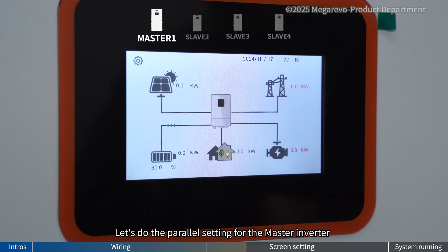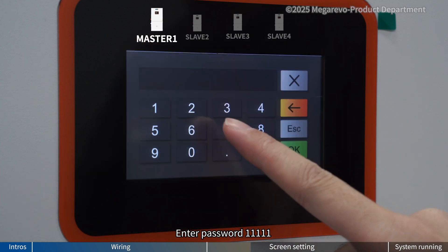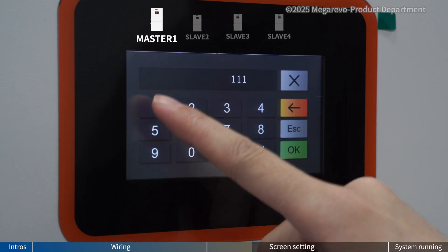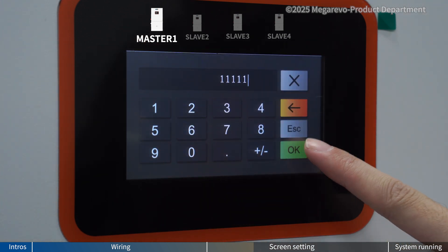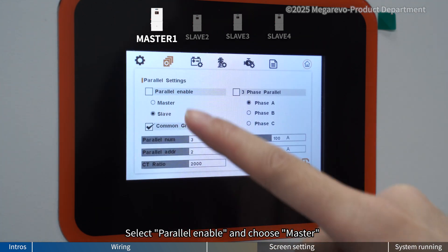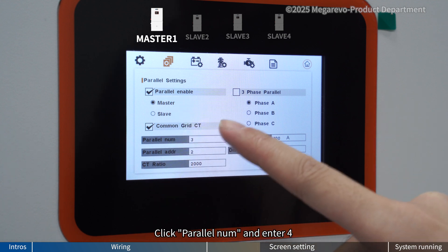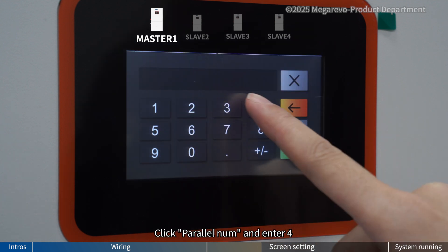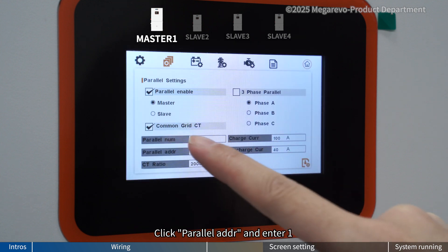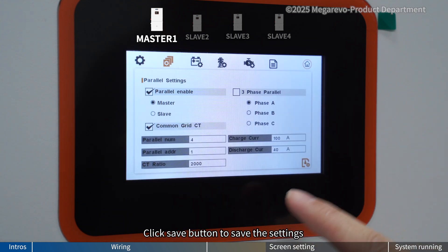Let's do the parallel setting for the master inverter. Click the setting button on the home page. Enter password 1 1 1 1 1. Click parallel setting. Select parallel enable and choose master. Click parallel number and enter 4. Click parallel address and enter 1. Click save button to save the settings.